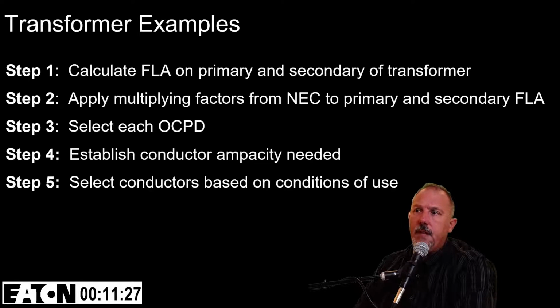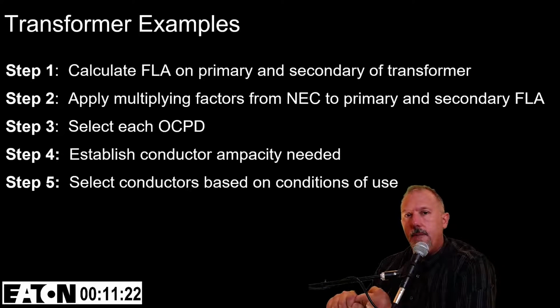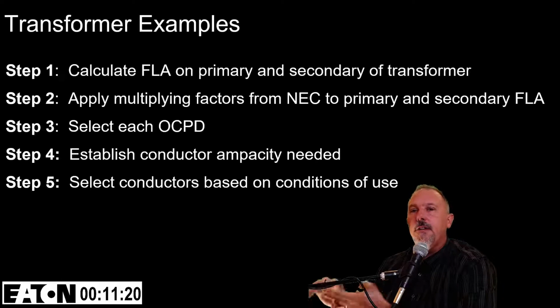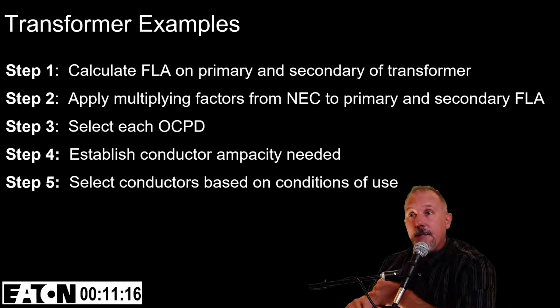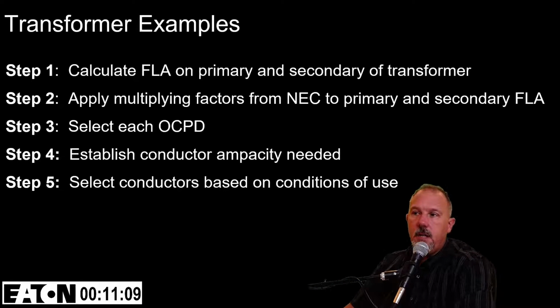We have to be mindful of the inrush current. So you calculate your full load amps, you add your multiplying factors, you select your overcurrent protective devices, then you establish the ampacity of the conductors that you need, and then you select those conductors based upon the conditions of use.